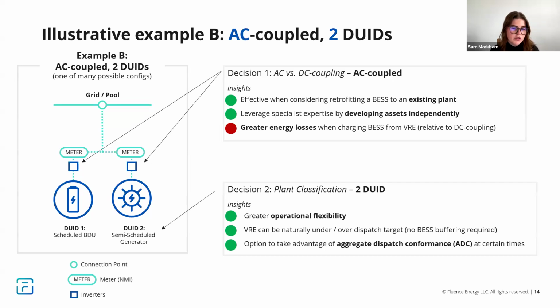Decision 2, so 2 DUIDs - this offers greater operational flexibility because you can have the battery operating as a scheduled bidirectional unit, but for the solar plant you can take advantage of it being a semi-scheduled generator and the flexibility that provides. VRE can be naturally under or over dispatching targets with no BESS buffering required, because as far as AEMO's dispatch instructions are concerned, they're 2 different assets. It's just that behind the connection point, reactive power needs to be consistently managed. And the third benefit of 2 DUIDs is there's the option to take advantage of aggregate dispatch conformance at certain times.